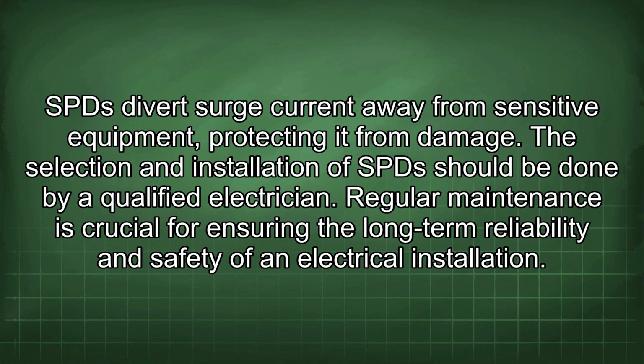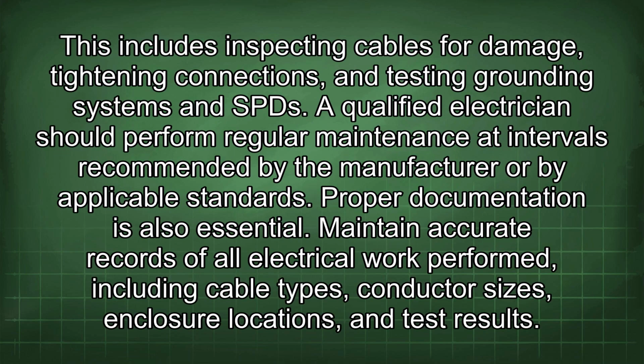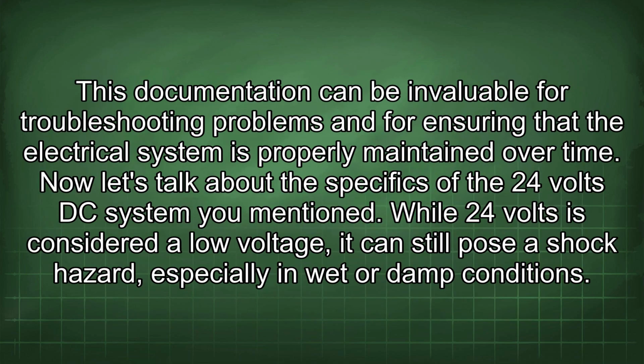Regular maintenance is crucial for ensuring the long-term reliability and safety of an electrical installation. This includes inspecting cables for damage, tightening connections, and testing grounding systems and SPD. A qualified electrician should perform regular maintenance at intervals recommended by the manufacturer or by applicable standards. Proper documentation is also essential. Maintain accurate records of all electrical work performed, including cable types, conductor sizes, enclosure locations, and test results. This documentation can be invaluable for troubleshooting problems and for ensuring that the electrical system is properly maintained over time.